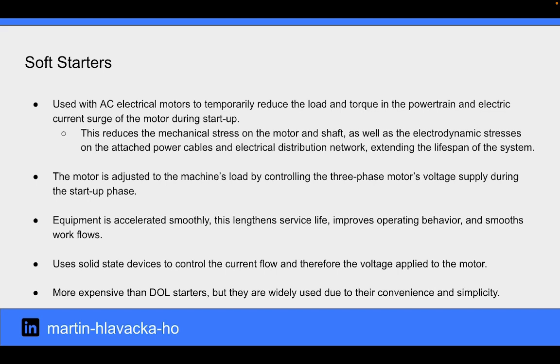The motor is adjusted to the machine's load by controlling the three-phase motor's voltage supply during the startup phase. Equipment is accelerated smoothly. This lengthens service life, improves operating behavior, and smooths workflows. Electrical soft starters can use solid-state devices to control the current flow and therefore the voltage applied to the motor. Soft starters are more expensive than direct-on-line starters, but they are widely used due to their convenience and simplicity.